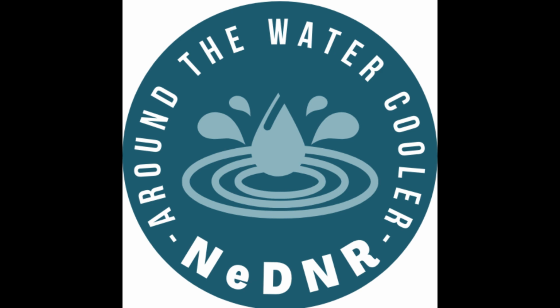And so you can use a variety of different methods. A bubbler and a radar are the two most common in our area. So you can fix a radar onto a bridge or a nearby stationary structure, and that will send a beam down to the river and back up to the radar, and that will tell you the river stage as it moves up and down. Or you can use a bubbler system where you bury an air bubble line near the stream bed, and that will constantly let out a little bubble. The instruments can then detect the pressure it takes to spit the bubble out, and that will tell you if the stage is rising or falling based on that pressure change.